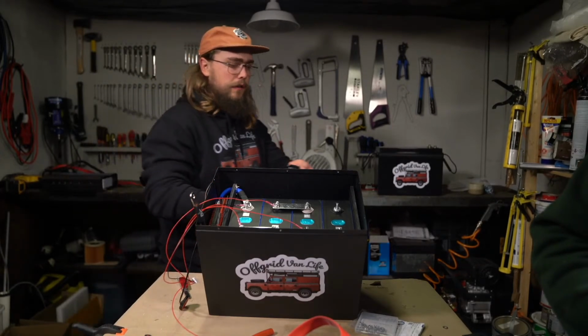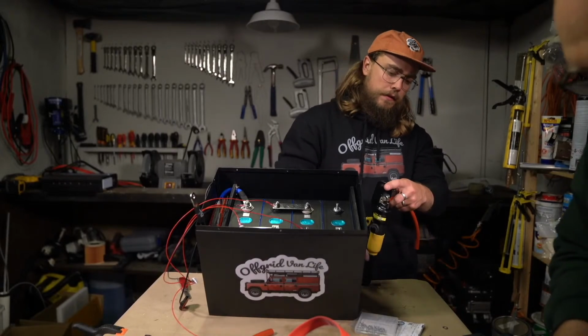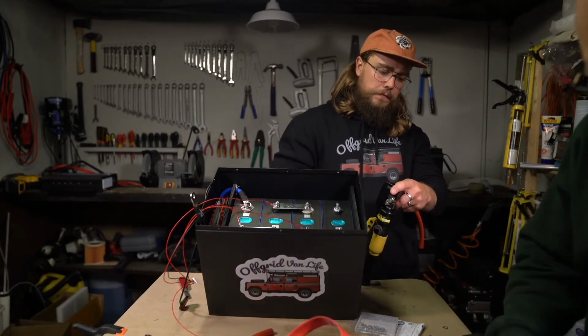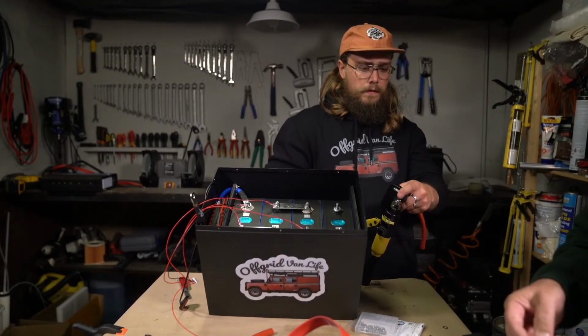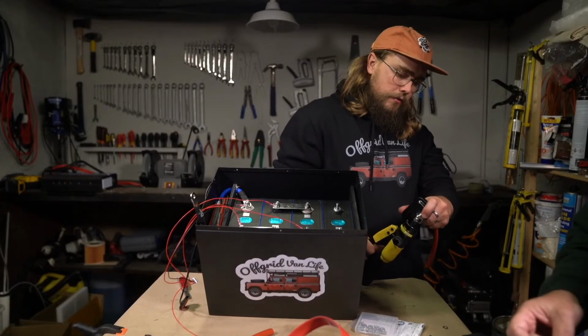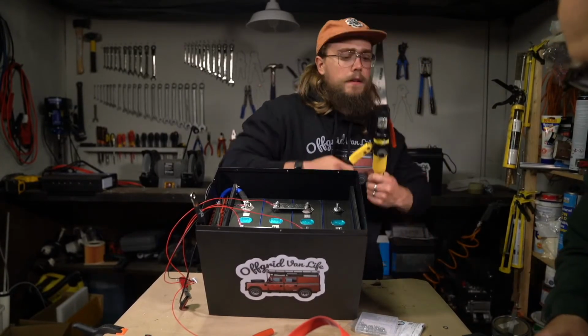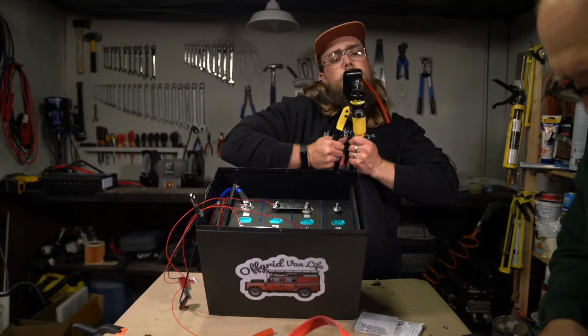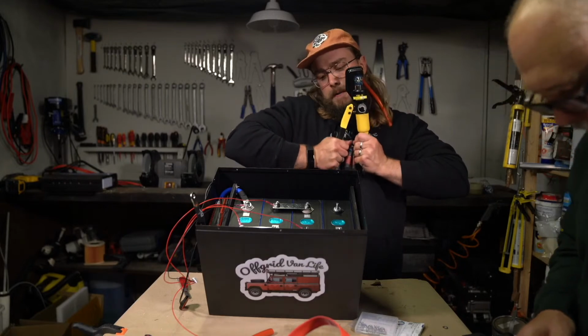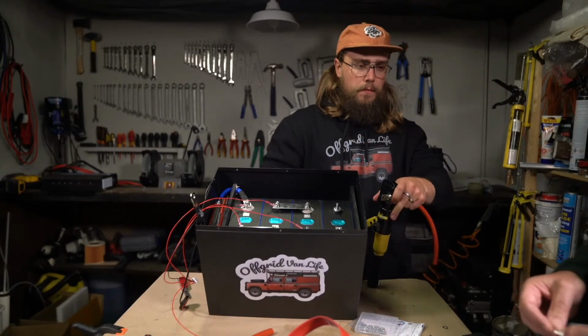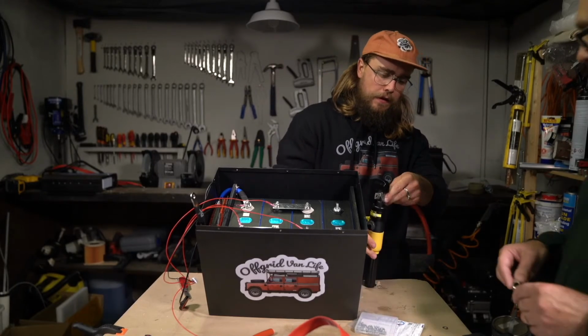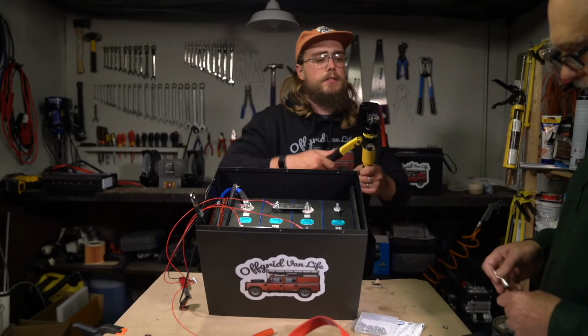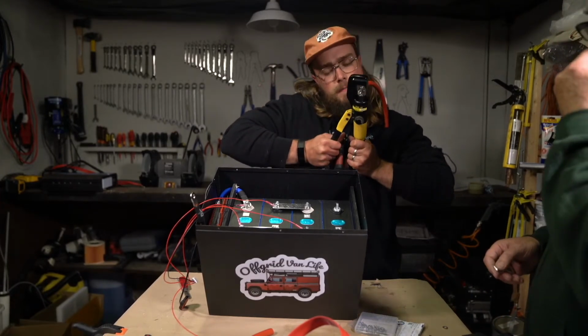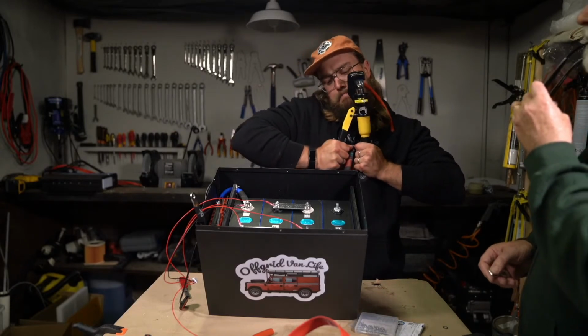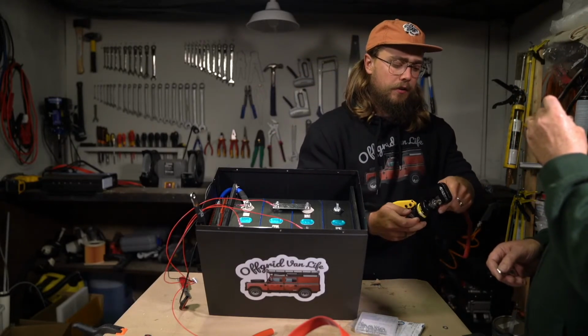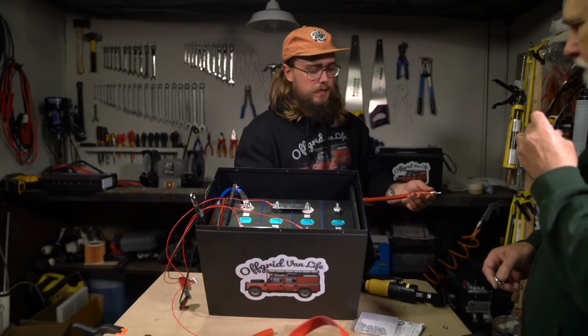I'm using a hydraulic hand crimping tool here. I'll usually crimp it on the table first until I get reasonable contact, holding the wire in, then crimp it properly until it won't go any further. With these lugs there's actually enough space to crimp twice on the shaft of the lug, to get a good connection. Another lug there, cool.